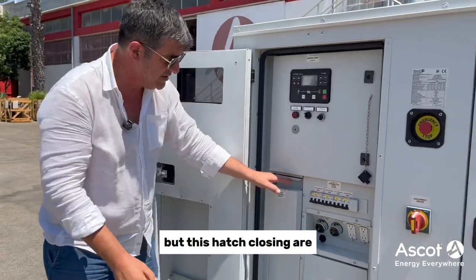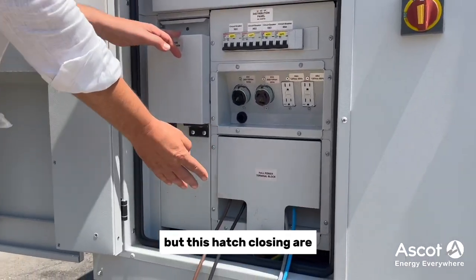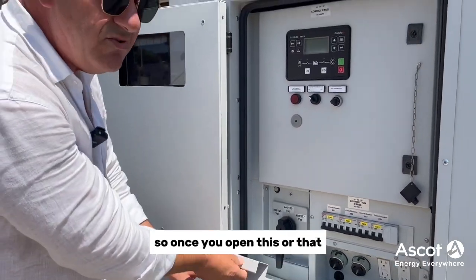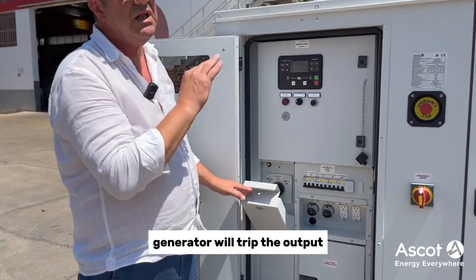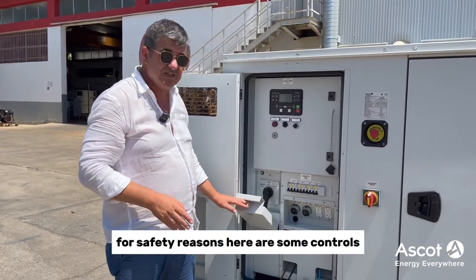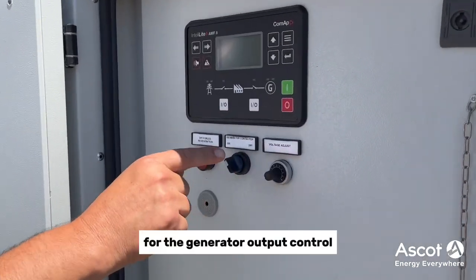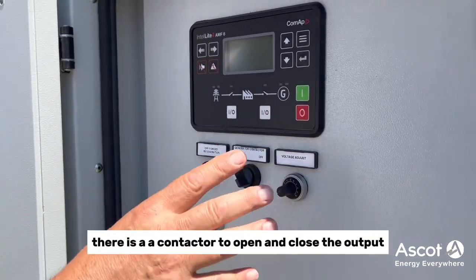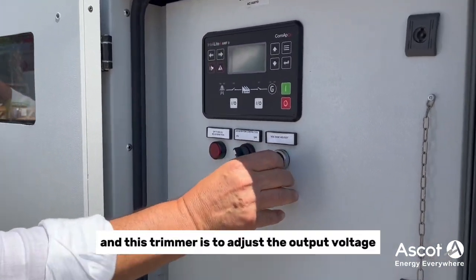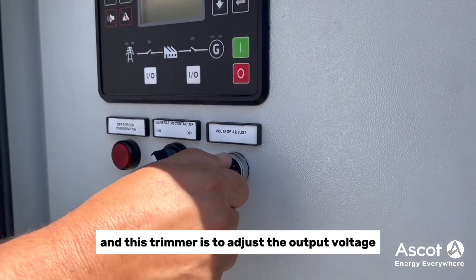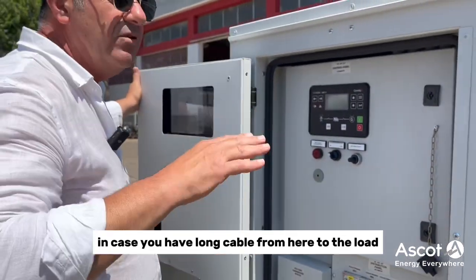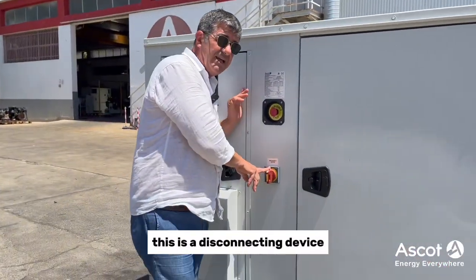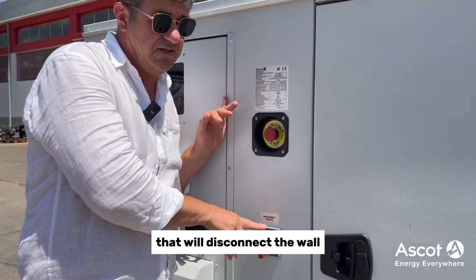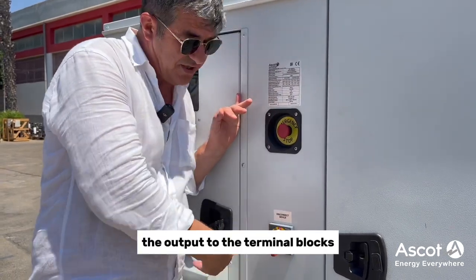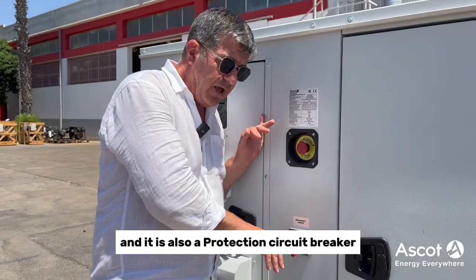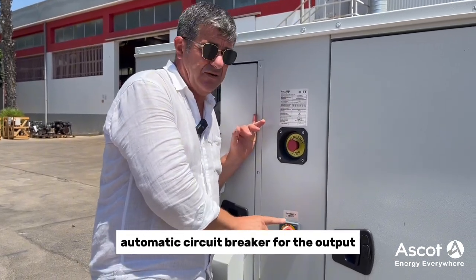But this hatch closing is protected through a micro switch. So once you open this or that, the generator will trip the output for safety reasons. Here are some controls for the generator output. There is a contactor to open and close the output. And this trimmer is to adjust the output voltage if needed, in case you have a long cable from here to the load. This is a disconnecting device that will disconnect the output to the terminal blocks, and it is also a protection circuit breaker, an automatic circuit breaker for the output.